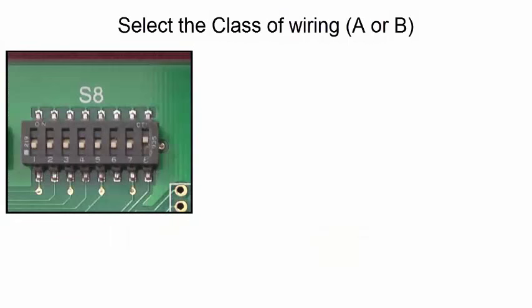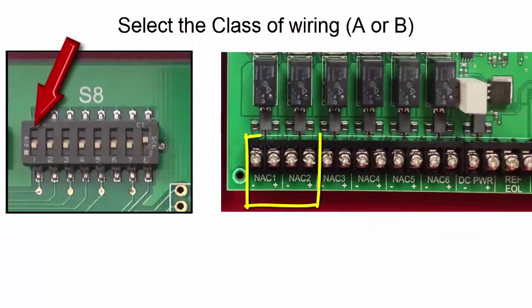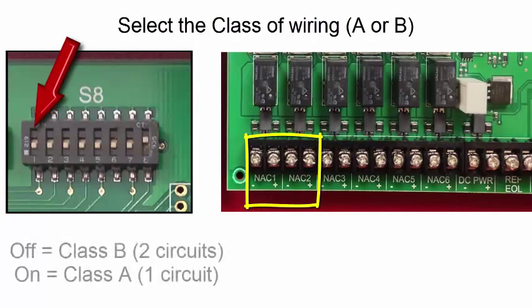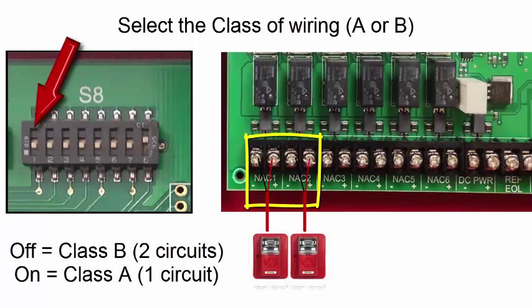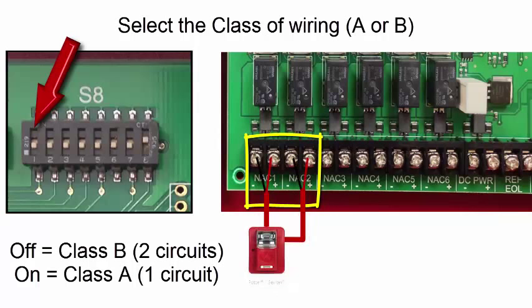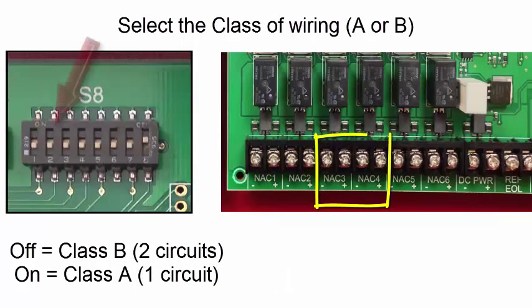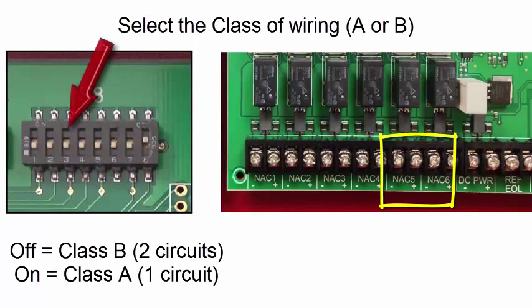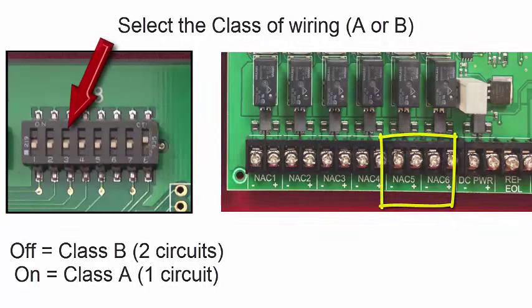Switch 8 also allows the installer to select the class or style of wiring for the NAC outputs. For example, DIP switch 1 of switch 8 sets the class or style of wiring for NAC 1 and 2. In the off position, NAC 1 and 2 will be class B. In the on position, it will be one class A circuit as seen here. DIP switch 2 of switch 8 sets the style of wiring for NAC 3 and 4. DIP switch 3 sets the style of wiring for NAC 5 and 6.